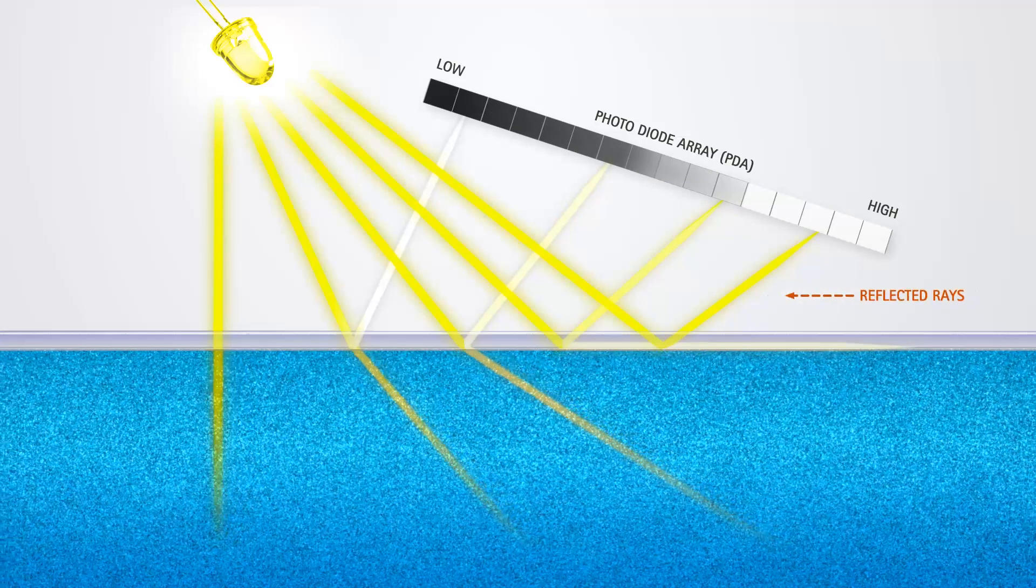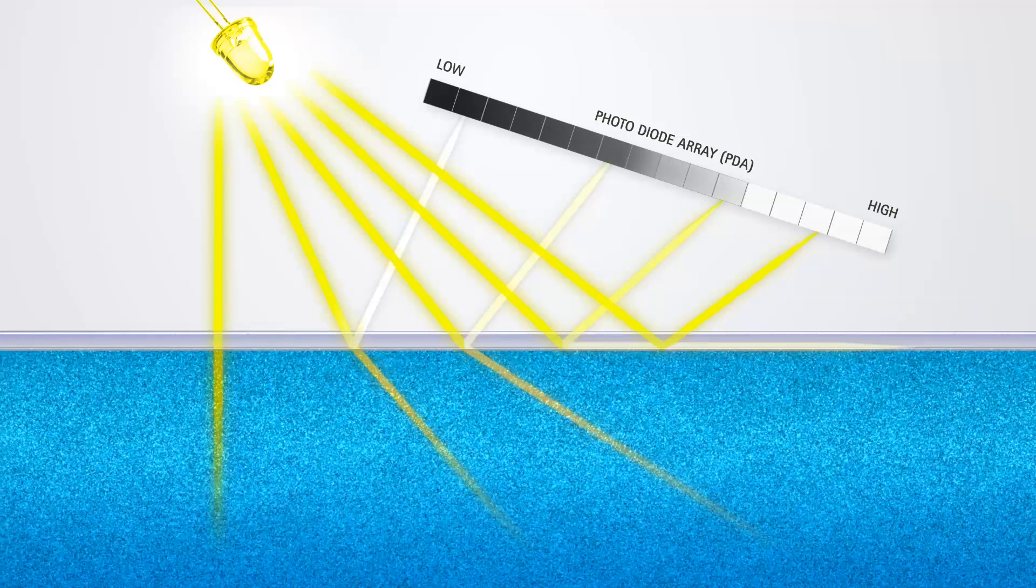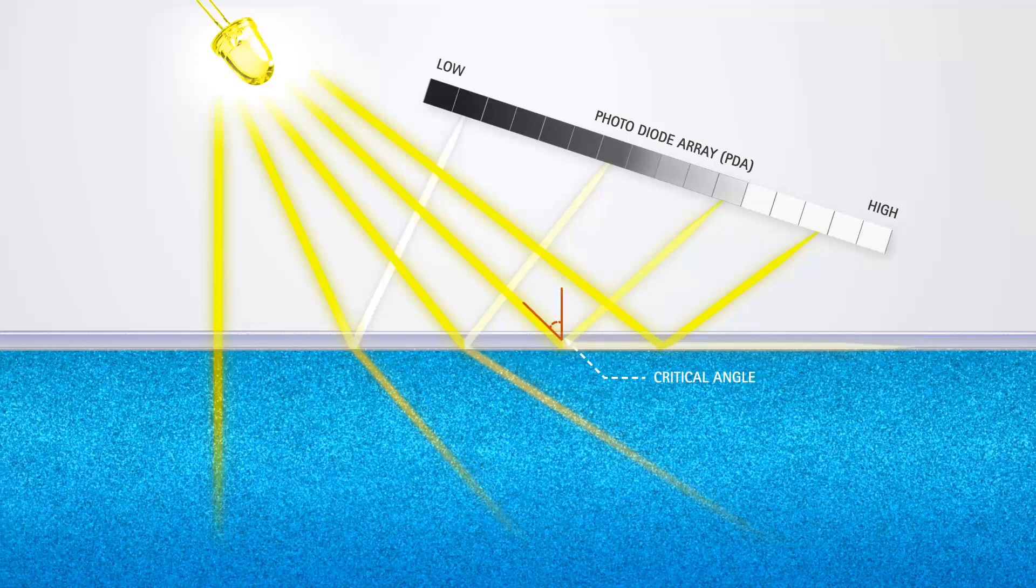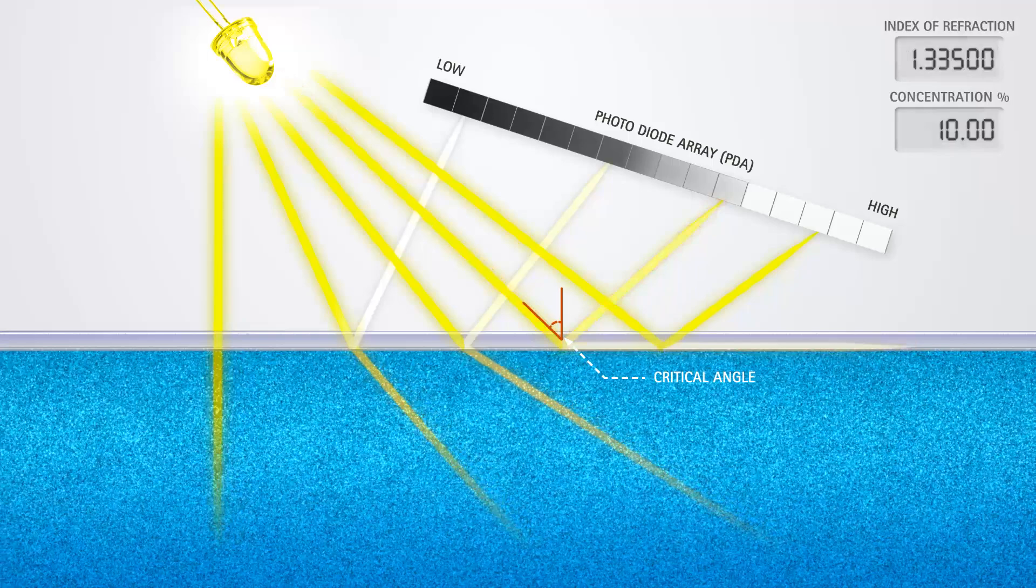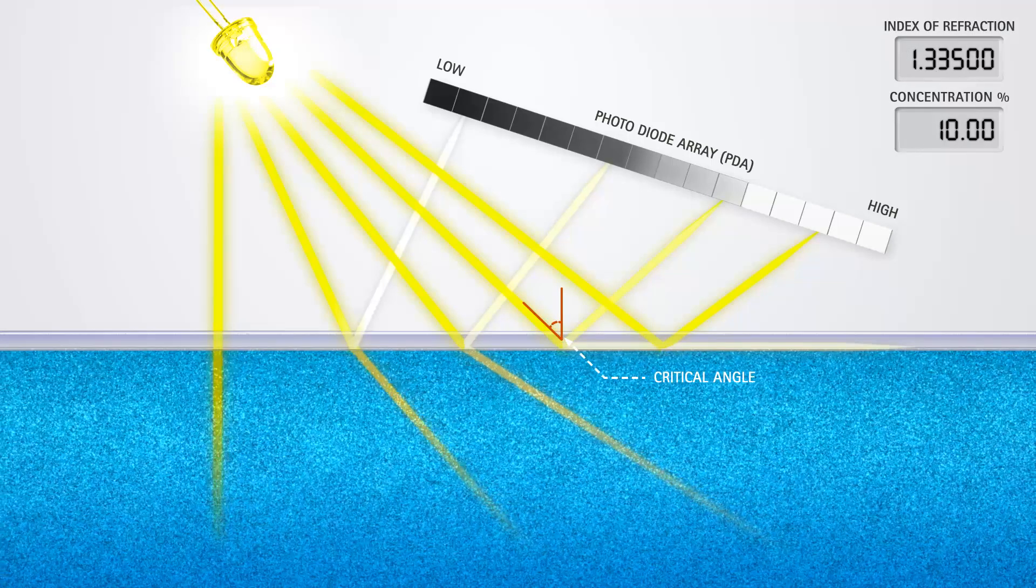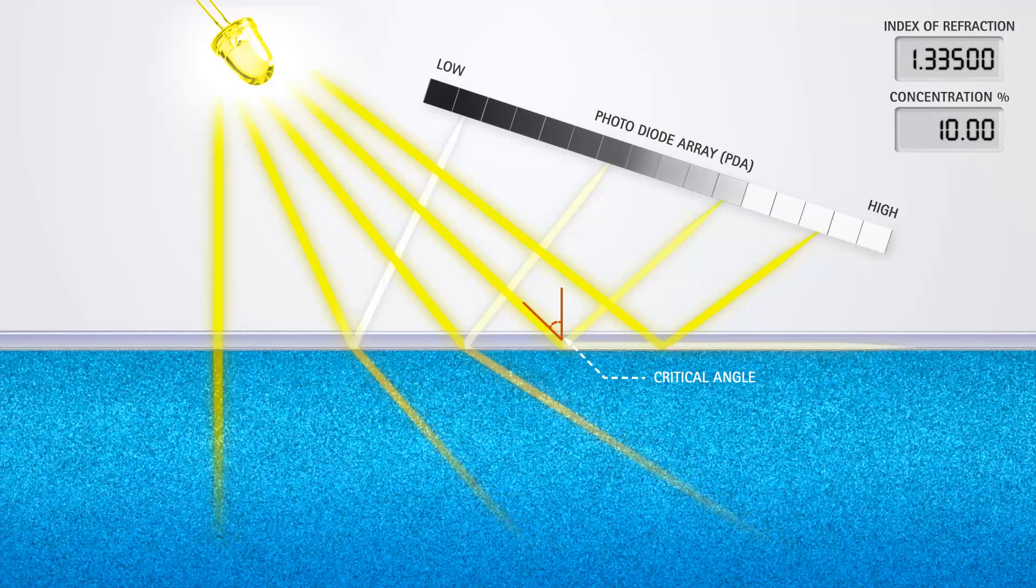At a critical angle, the light no longer refracts into the liquid, but completely reflects back to the PDA. The Index of Refraction is calculated from the critical angle using Snell's Law.